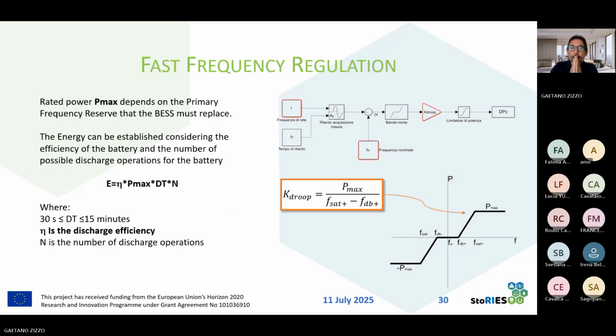And how can we size a battery for this kind of service? Well, it's not so simple, because it depends on the number of batteries that we will use. We can start sizing by choosing the maximum power of all the batteries that are connected to that area for providing that service. So we can calculate Pmax, that is the sum of all the rated power of all the batteries that provide the service, in this way.